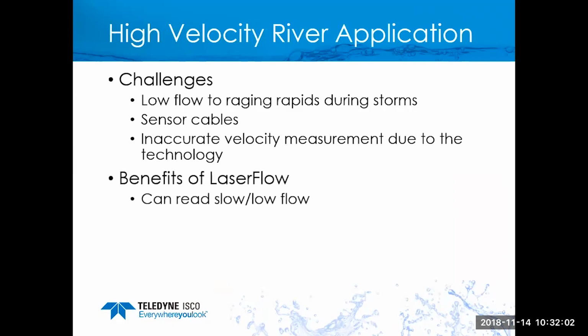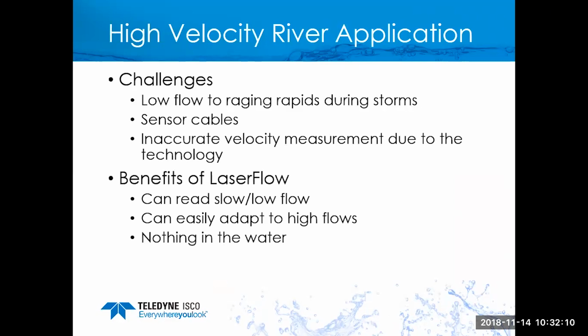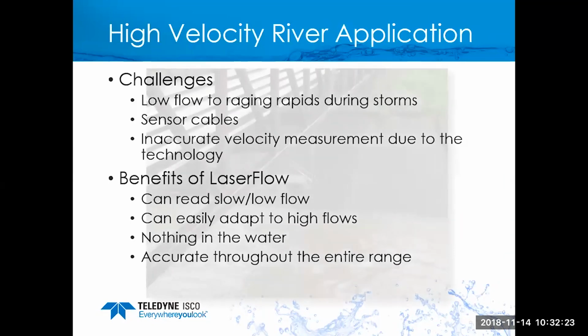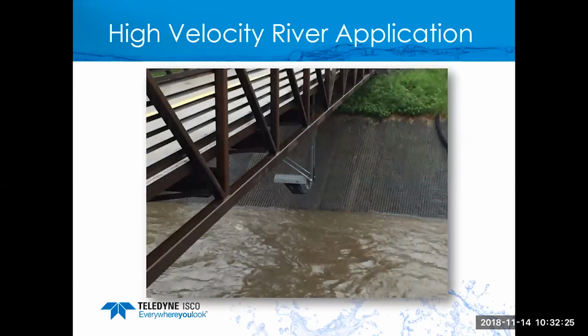The benefit of the laser is it can read the slow flow, it can read the low flow, and it can easily adapt to high flow conditions. So it can go from a trickle, nothing in the water to see, so not a lot of particles. It's going to be accurate through the entire range of the event. So again, a tenth of an inch all the way up to pretty much full pipe or full channel.